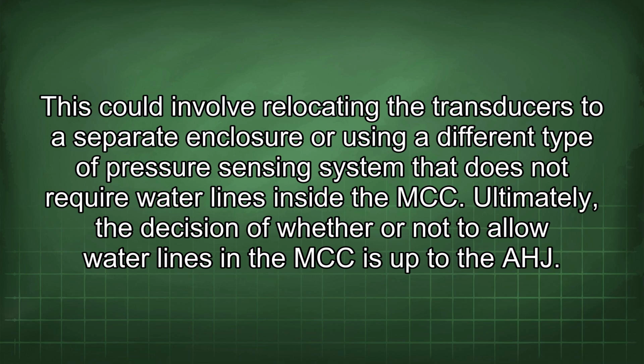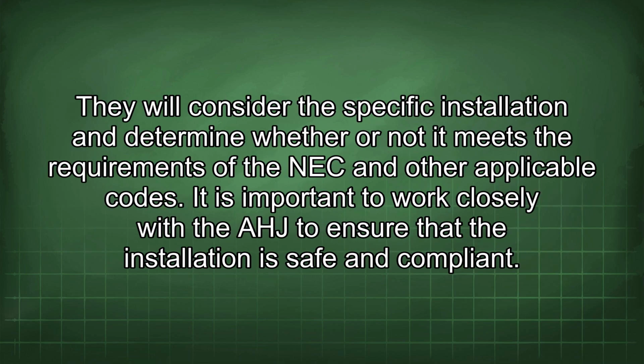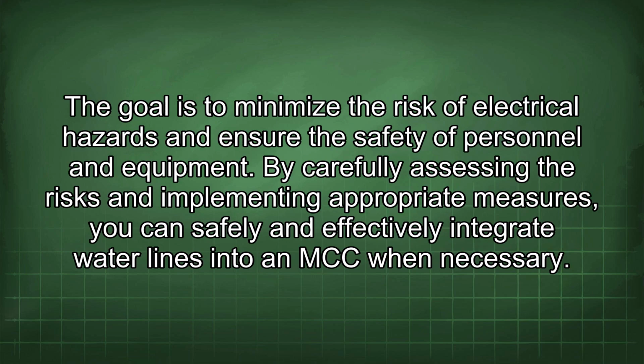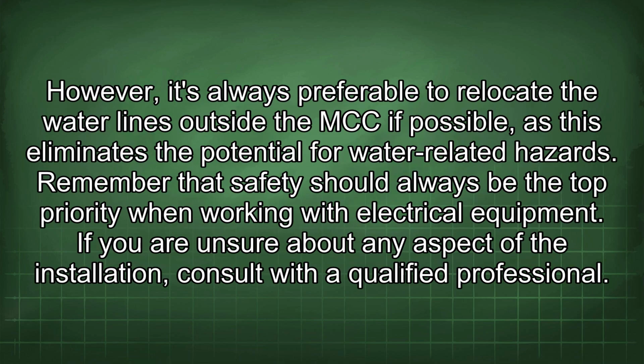Ultimately, the decision of whether or not to allow water lines in the MCC is up to the AHJ. They will consider the specific installation and determine whether or not it meets the requirements of the NEC and other applicable codes. It is important to work closely with the AHJ to ensure that the installation is safe and compliant. The goal is to minimize the risk of electrical hazards and ensure the safety of personnel and equipment. By carefully assessing the risks and implementing appropriate measures, you can safely and effectively integrate water lines into an MCC when necessary. However, it's always preferable to relocate the water lines outside the MCC if possible, as this eliminates the potential for water-related hazards. Remember that safety should always be the top priority when working with electrical equipment. If you are unsure about any aspect of the installation, consult with a qualified professional.